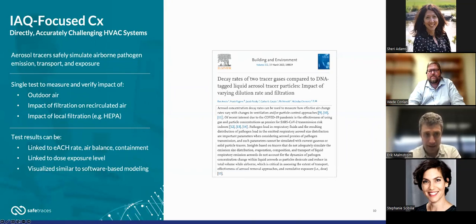The value of using an aerosol challenge method is that in a single test we can measure and verify the impact of outdoor air, and whether increasing the outdoor air fraction is having a measurable benefit in reducing exposure and containing aerosol contaminants. In the same test, we also test the filtration impact on these particles, both filtration provided by air handling units and local filtration, like in-room HEPA units, which have become very popular during the pandemic.